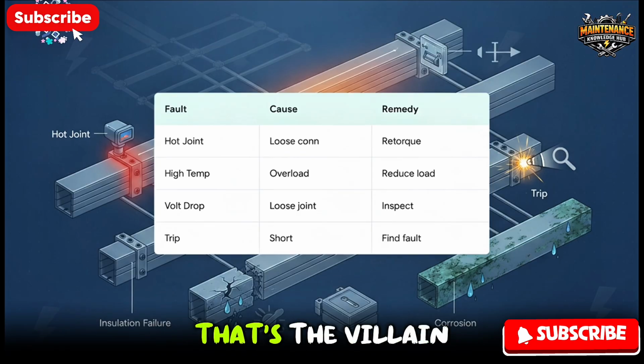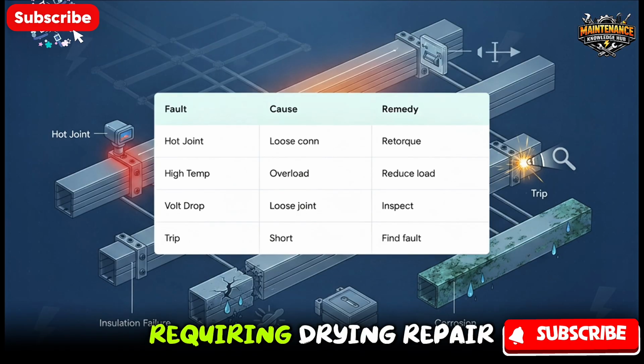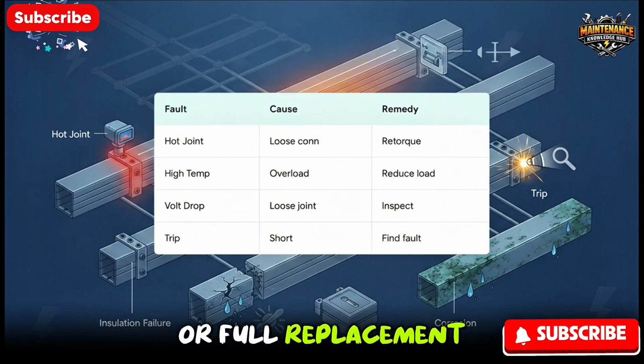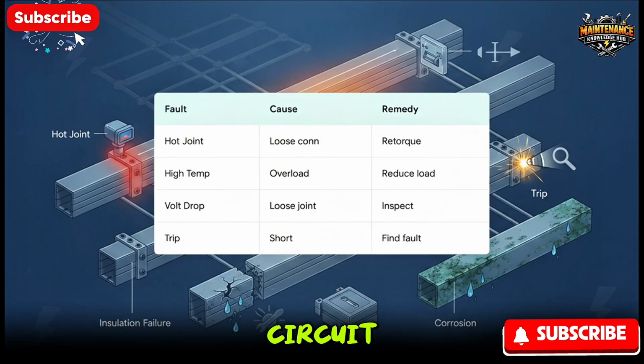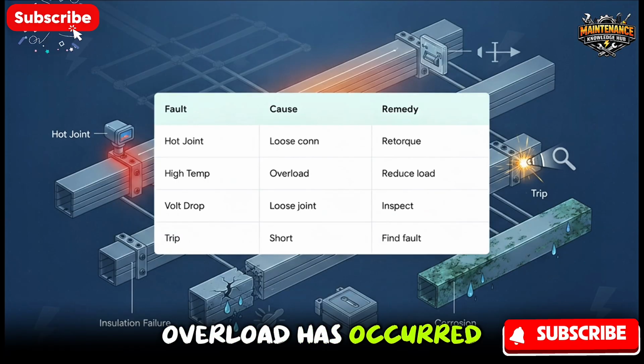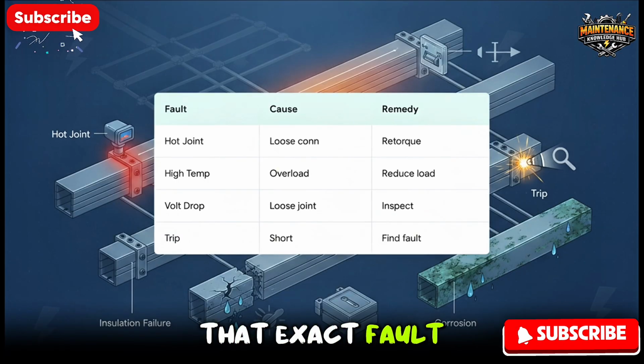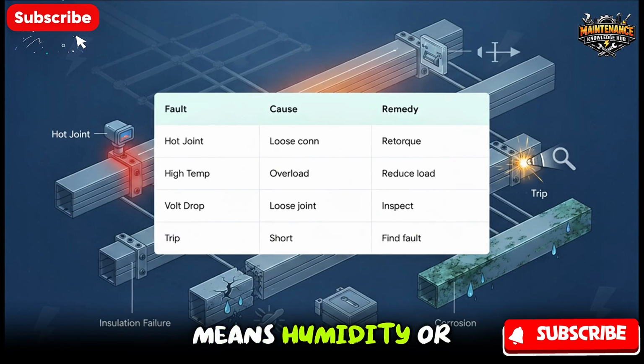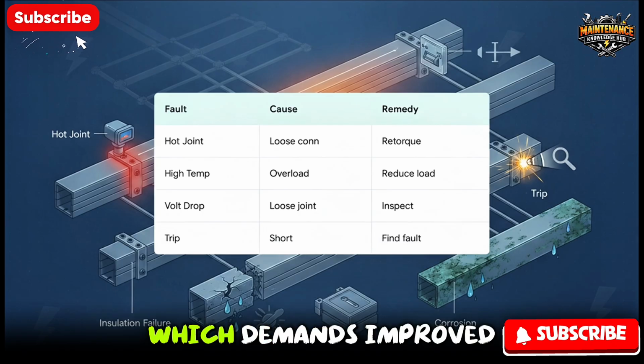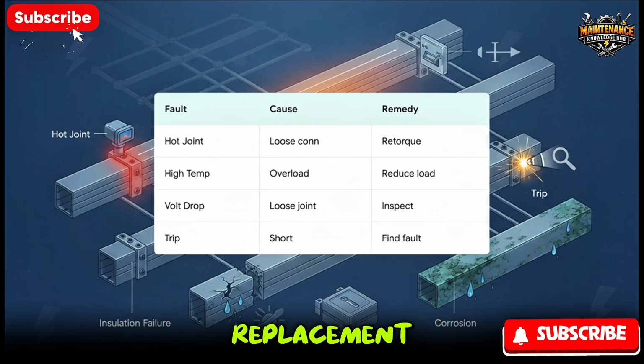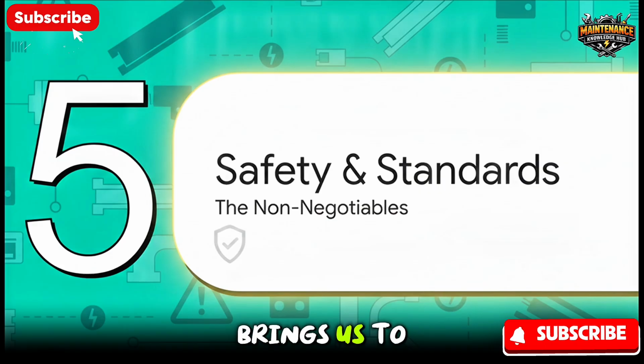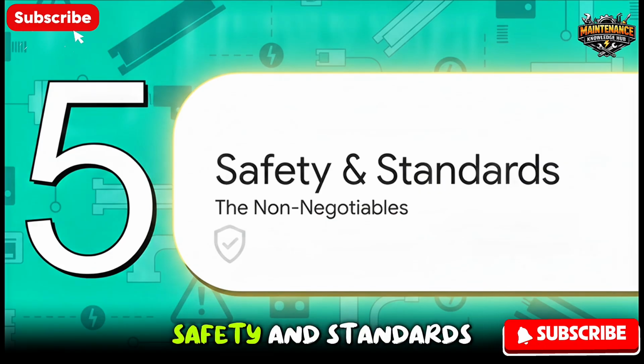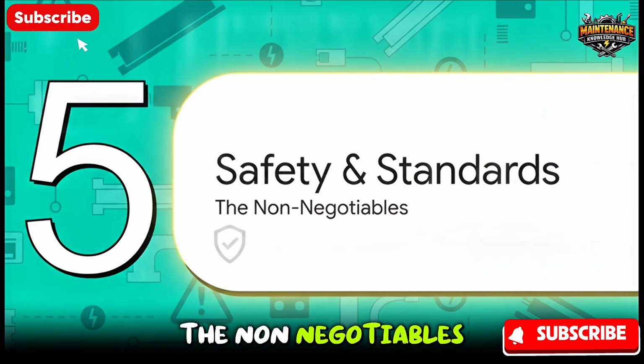Insulation failure? That's the villain of moisture or aging, requiring drying, repair, or full replacement. A breaker trip means a short circuit or a severe overload has occurred, and you've got to hunt down that exact fault. Finally, corrosion means humidity or water has breached the enclosure, which demands improved sealing and parts replacement right away. Which brings us to Section 5, Safety and Standards, the non-negotiables.